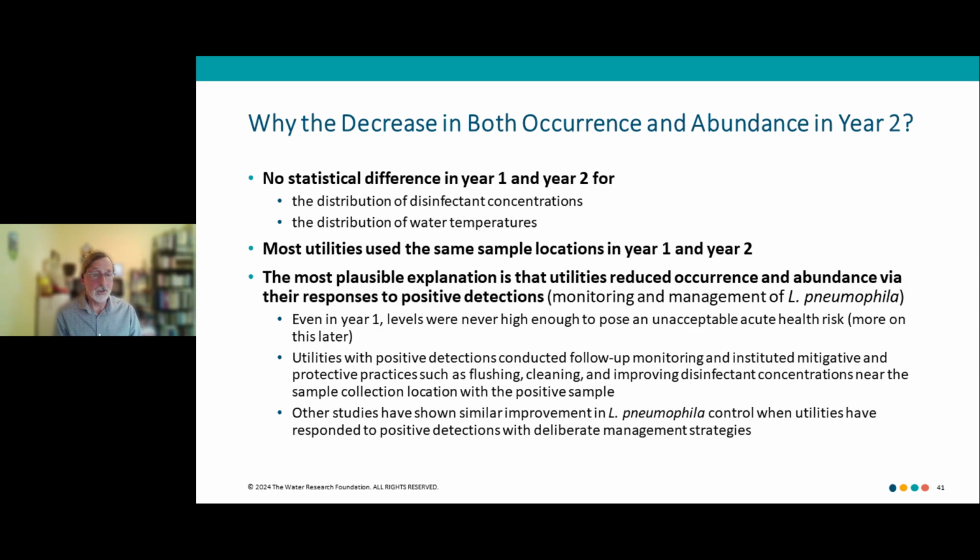Utilities with positive detections or positive samples did follow-up monitoring. They instituted mitigative and protective practices like Gary was talking about, and it appears that those are the actions that caused year 2 to look better than year 1. And this is a success story. This says, hey, utilities, if you do monitoring and you supplement your water quality management activities to directly address Legionella, you can make a difference.